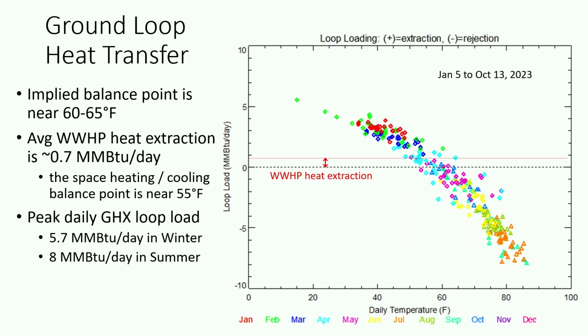I like this graph because it shows the loop load. Heat extraction is positive, and heat rejection is negative. You can see we have a pretty well-defined trend with different slopes for heating and cooling. The other thing I'll point out is the water heat pumps, which did domestic hot water heating, extracted about that much most of the time. The point where the load on the loop crossed zero, from positive to negative, was about 60 or 65 degrees, but the balance point for space conditioning was lower than that. So the heat extraction had lowered our balance point on the loop in terms of load.